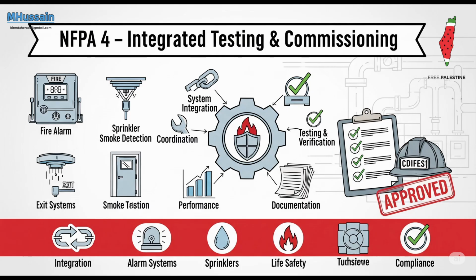Okay. But then a more complex building, say a high-rise. Oh, absolutely requires a plan. Imagine a high-rise with sprinklers, fire alarm, elevators, plus maybe a complex stair pressurization system for smoke control, and automatic closing fire-rated doors tied in, and maybe advanced HVAC smoke control sequences. Way more interactions. Exactly. The intricate interactions between all those systems, they absolutely demand a formal, detailed, integrated test plan.